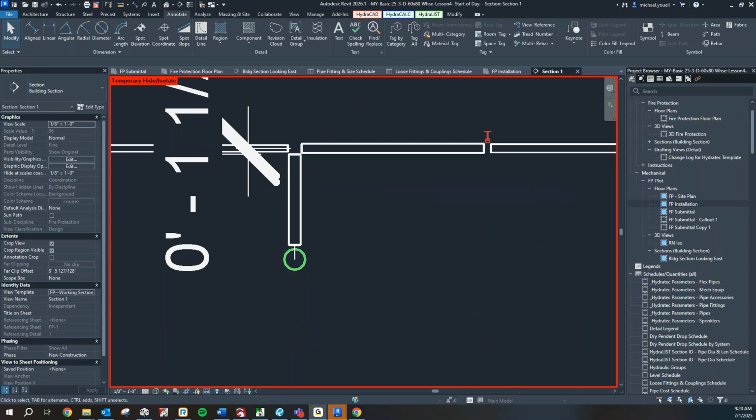I'm gonna claim we actually do this, Michael. I draw a 3-inch main, a 2.5-inch main, a 3-inch main, a 4-inch main, a 6-inch main, and an 8-inch main. And then I take a 1-inch pipe and connect it into it, a 1.25-inch pipe and connect it into it, a 1.5-inch pipe and connect it into it. And then I measure all of those and I compare it against the cut sheet for the ASC groovelets, and I compare it against the cut sheet for the Ward cast iron tees, and I verify all those takeouts.